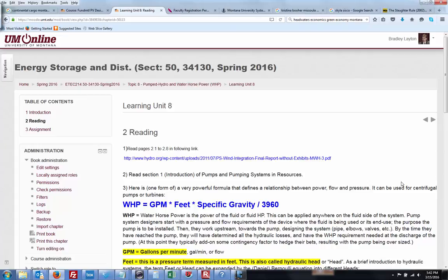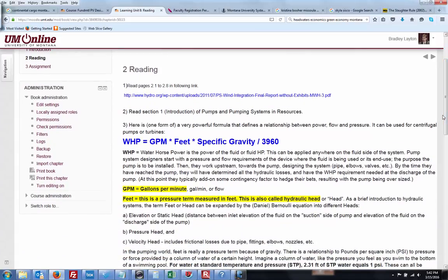Very powerful formula defines a relationship between power flow and pressure. So, water horsepower. I'm not going to bother that much with the derivation of this. I normally do, but in the interest of time, think of it this way. The more gallons, and this is again getting back to our across and through variables, I've beaten that one to death, but the more fluid that's flowing through times the pressure, so this is the through variable, this is the across variable, and then this is basically the density and another factor that make the units work out. Because this guy's in gallons, that one's in feet, this is specific gravity. Yeah, it's all over the place. So 3960 takes care of the units.